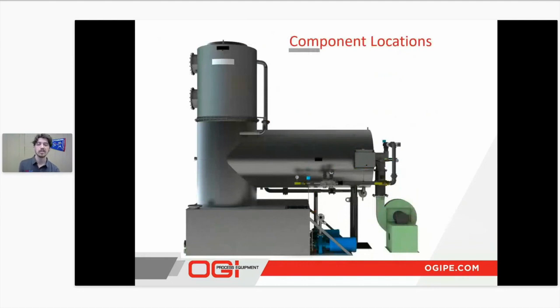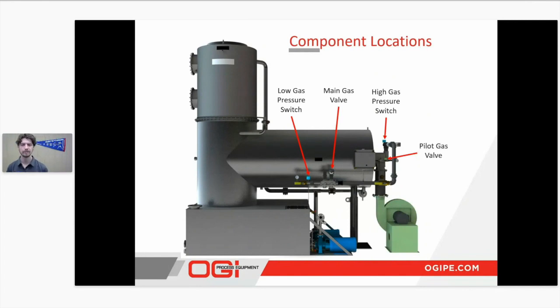So flipping over to the gas train side, we're going to have 4 components over here of note. So that'll be our low gas pressure switch, our main gas valve, our high gas pressure switch, and our pilot gas valve. So essentially, at our pilot gas valve, we want to make sure that we have typically around 3 psi for full fire on these units. And another thing that I mentioned, we have the specifications listed on each spec sheet for them, to properly size a regulator for your facility. That way we have no issues with our gas going through.